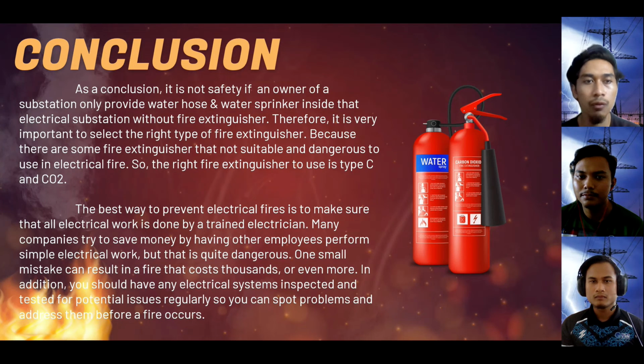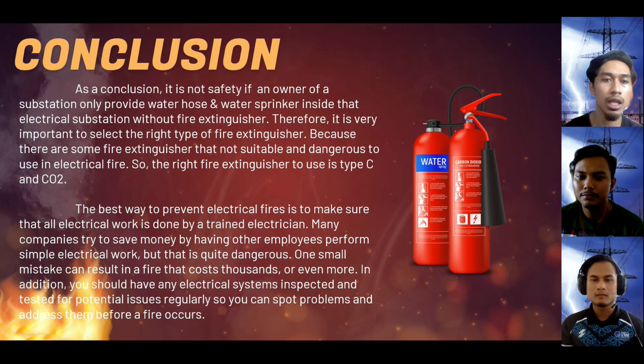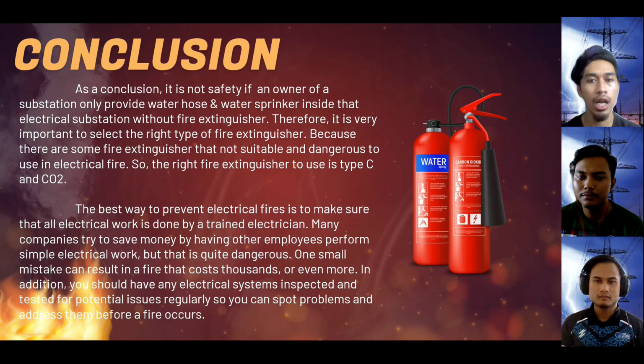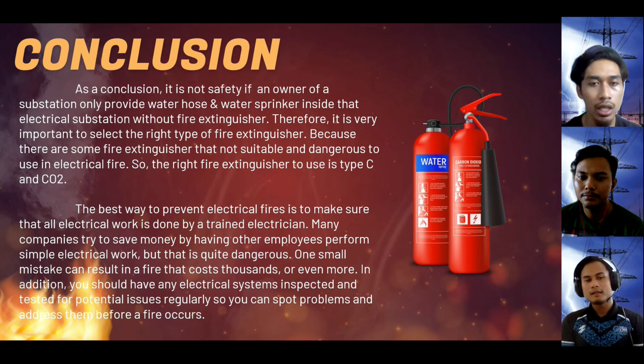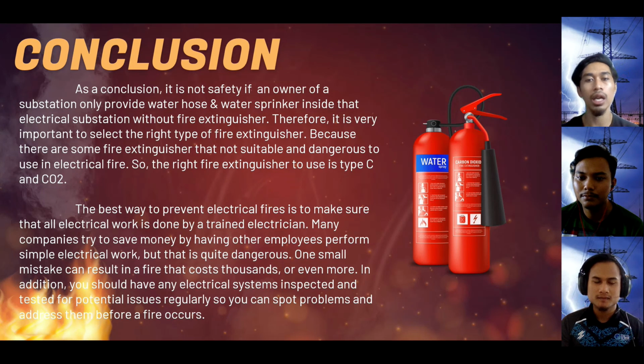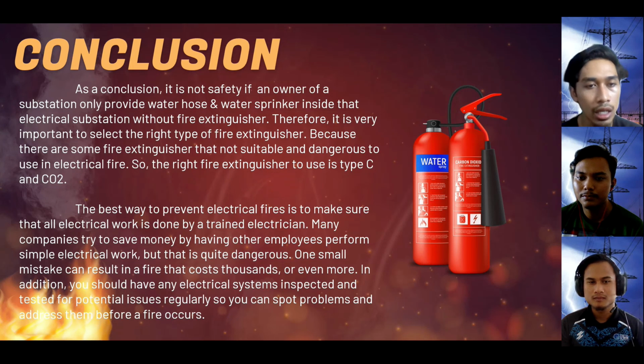As a conclusion, it is not safe if the owner of a substation only provides a water hose and water sprinkler inside the electrical substation without a fire extinguisher. Therefore, it is very important to select the right type of fire extinguisher, because some fire extinguishers are not suitable and are dangerous to use on an electrical fire. The right fire extinguishers to use on an electrical fire are Class C and CO2.